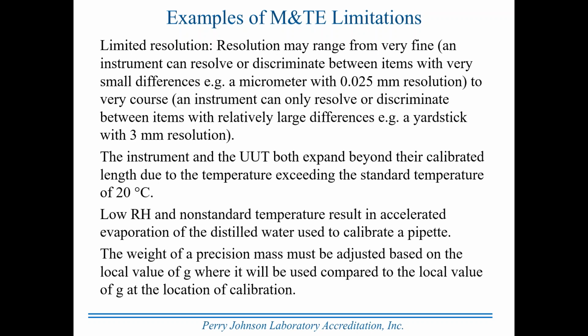So typically when you have mass calibrated, the people performing the calibration need to know the value of G at your location, and they adjust the weight so it will display the correct weight at your location, even though it will not at theirs because G is different. So these are some of the measurement and test equipment limitations. It's just a small example. There are many, but this hopefully gets you in tune of thinking of what might be changing and what might be the magnitude of those changes of all aspects of a measurement or calibration process.